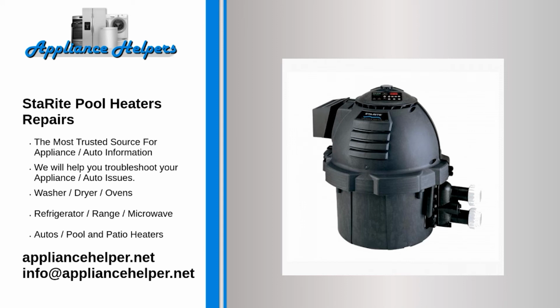Faulty thermostat. If you have determined that the thermostat is set correctly, you may have a thermostat that is faulty or out of calibration. Heat exchanger has lime or calcium buildup. Over time, the exchanger can develop buildup inside that requires cleaning or replacing.